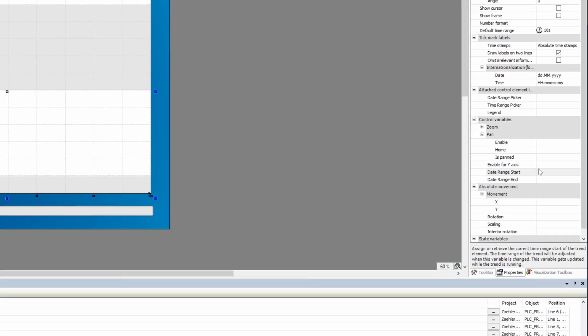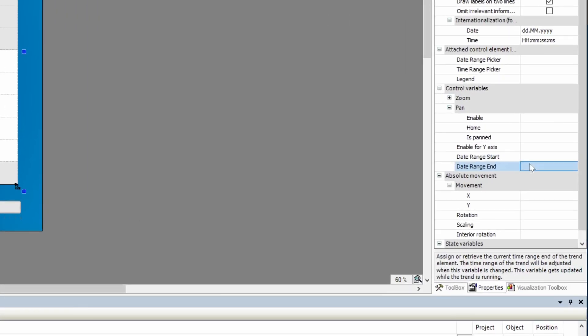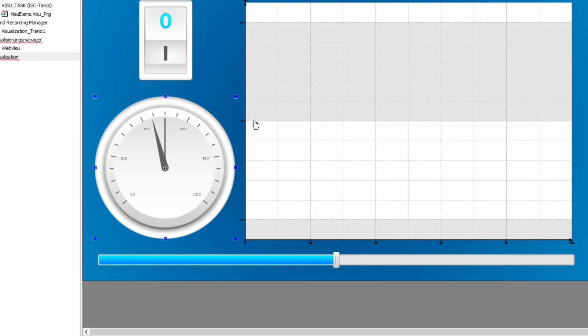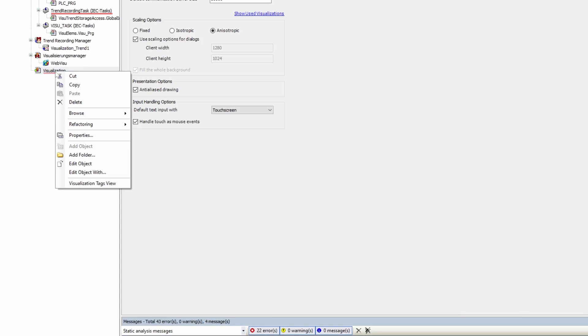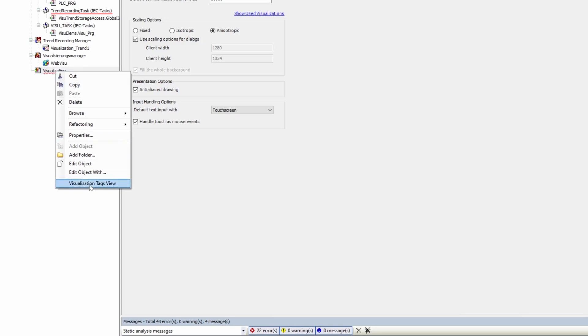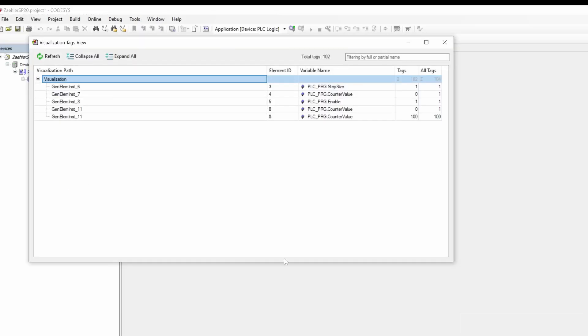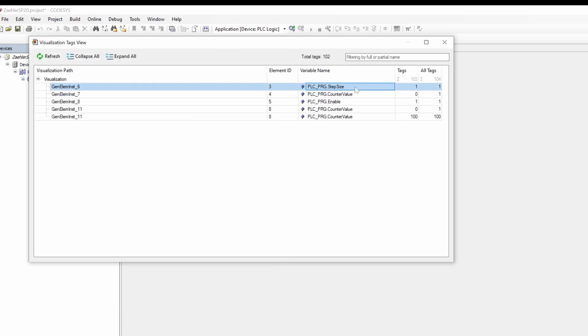The trend functionality in the CodeSys visualization now supports the configuration of start and end time for specific time periods. A second arrow can be displayed for measuring devices and the scroll area within the frame is determined dynamically. You can also flash the text color. The tag view visualization provides a detailed overview of the counted tags for application-based licenses, listing used variables of tags and showing the visualization call tree.